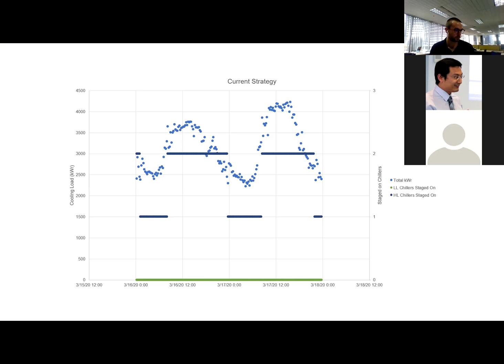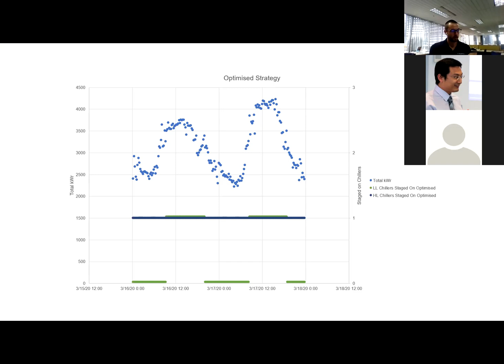But the way our optimized strategy has come out, we would be just running one of those high load chillers, the lead high load chiller, and then bringing the low load on at certain times of day to cover the rest of that cooling load, rather than staging the additional high load chiller on. And yeah, a reasonable amount of the energy savings were derived in this region.